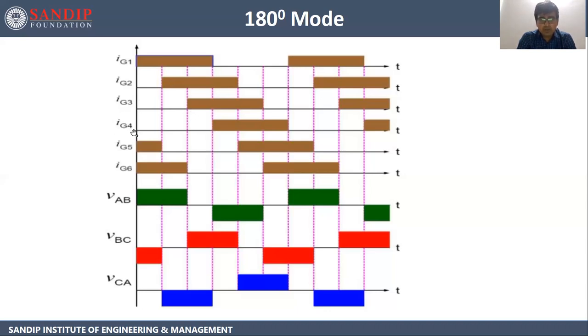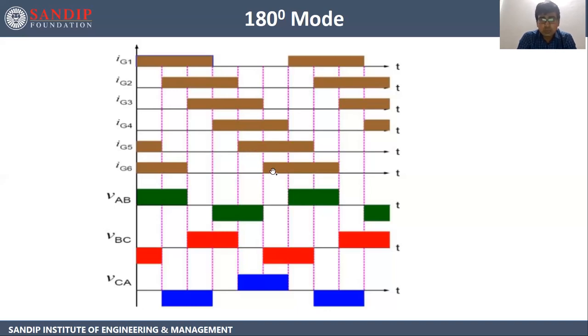Thyristor 4 will be triggered for 180 degrees (60 + 60 + 60). Then thyristor 5, and then thyristor 6. For the sixth thyristor, the cycle is shifted by 60 degrees with the remaining 120 degrees on the other side. Each cycle totals 360 degrees, with the six thyristors each separated by 60-degree intervals.